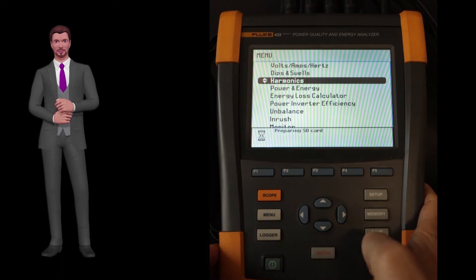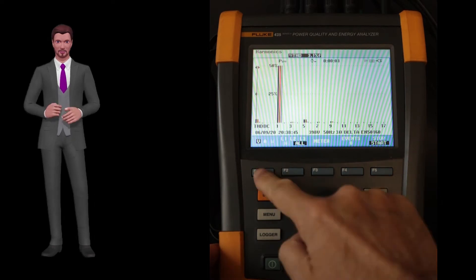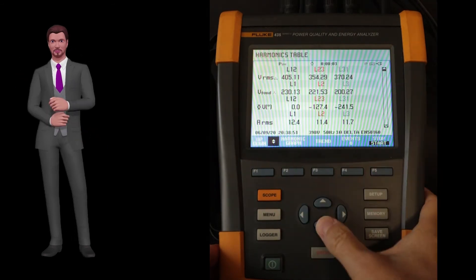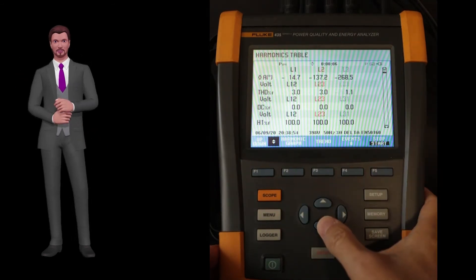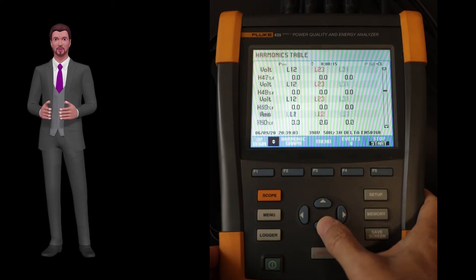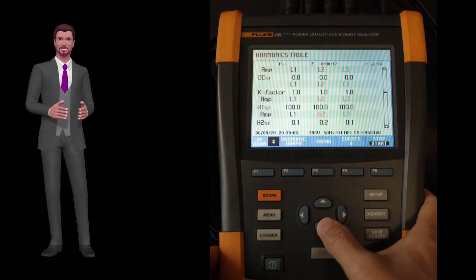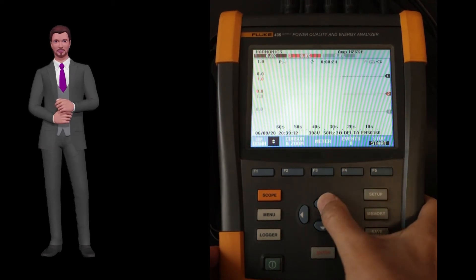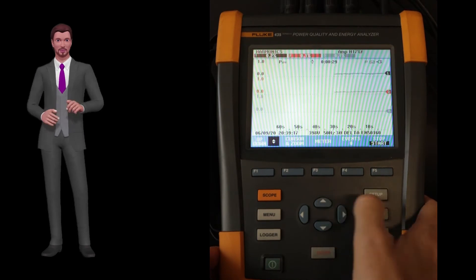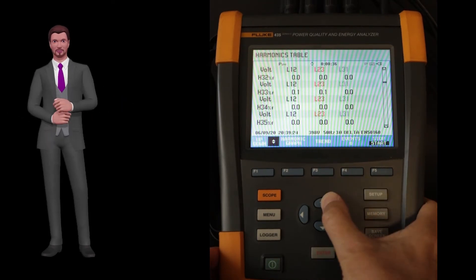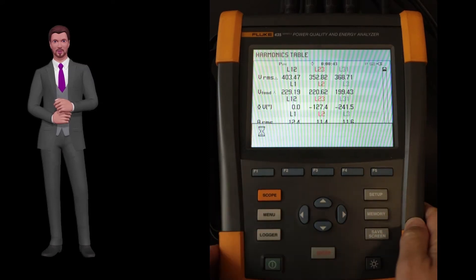The harmonics function will allow us to measure and record the voltage, current, and power harmonics up to the 50th harmonic, its associated THD, and also the interharmonics. Data can be viewed in numerical, trend, or frequency spectrum form with typical vertical bars. Given the large number of nonlinear loads in industrial facilities, it is essential to know how to analyze these harmonics.